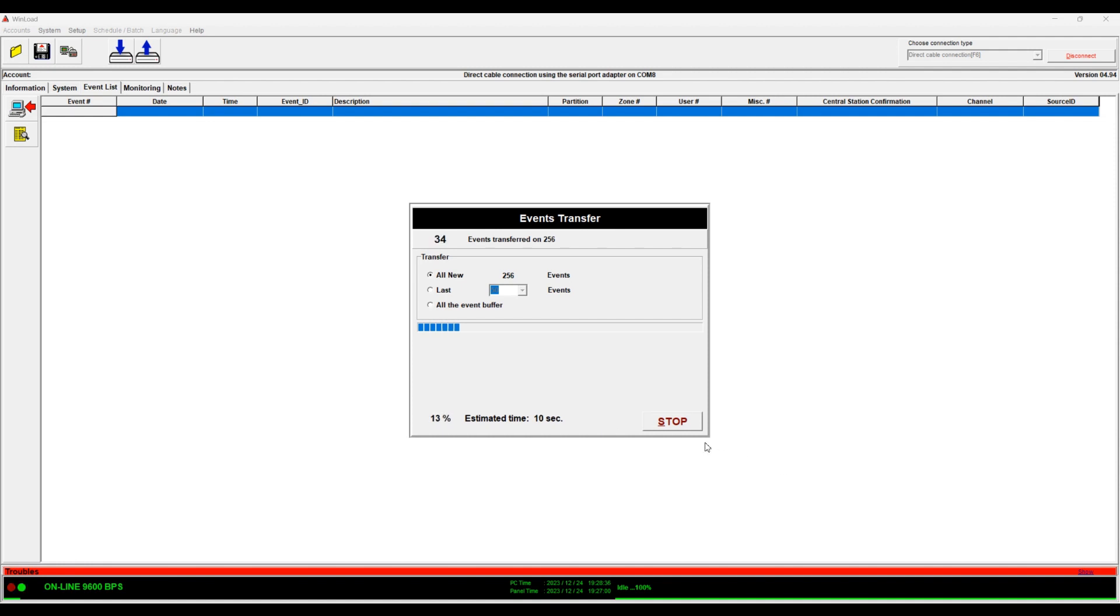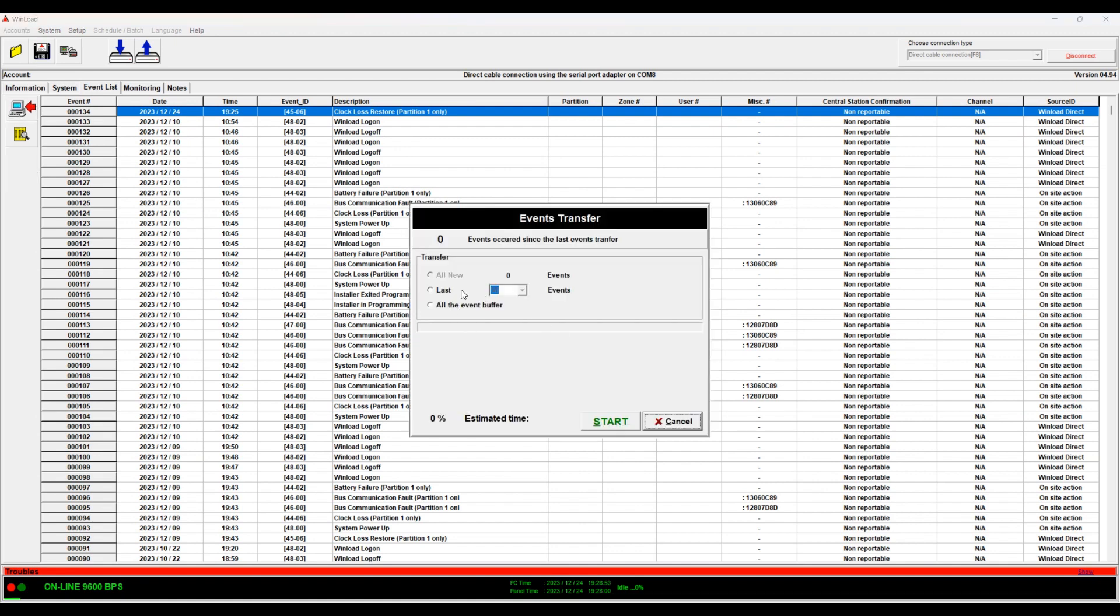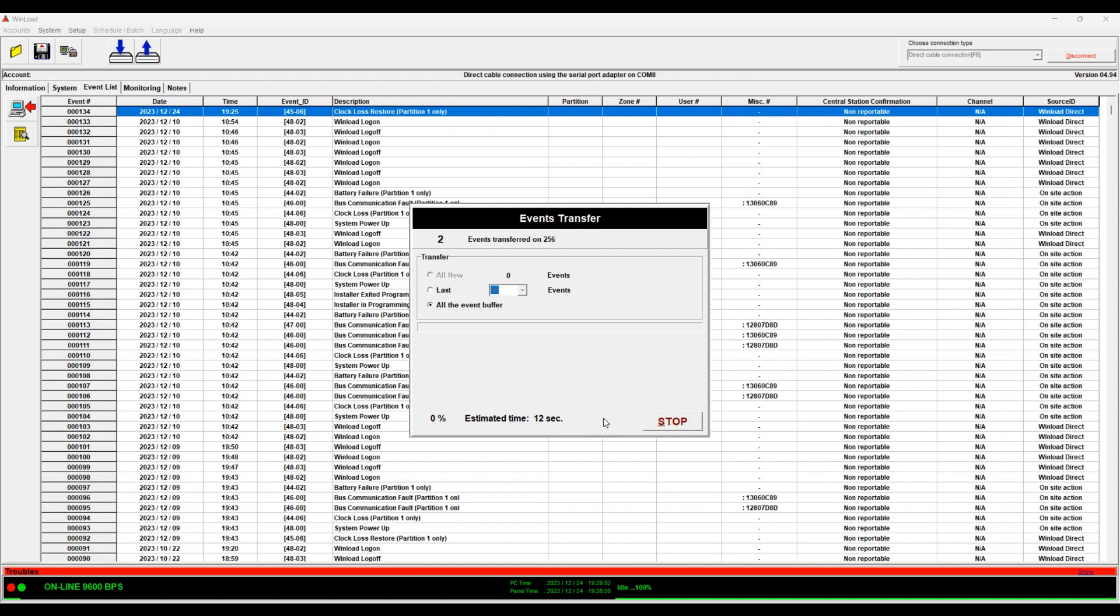If you click Stop, then the next time you're not going to be able to use All New, then you have to use All Event Buffer. Let me show you. So like this, it will download whatever it was able to download, then the next time you'll show zeros. There might be more because I cancelled midway, so I would have to download all event buffer to get the rest of the events. So try not to cancel whatever you choose. Try not to cancel, otherwise you would have to download all event buffer. When you're downloading using the serial port or IP, it's not a big deal, but if you're doing this over the phone, it could take an hour or more, so keep that in mind.